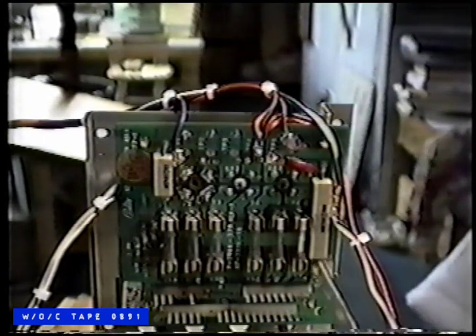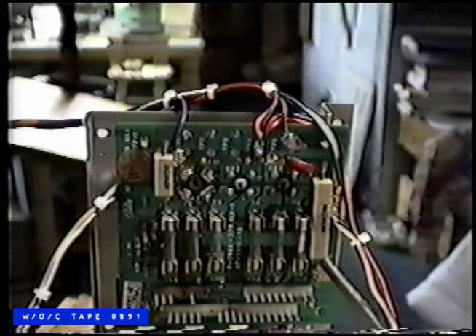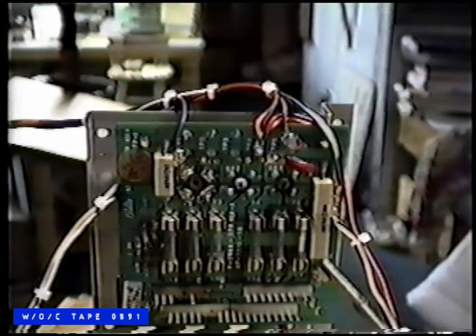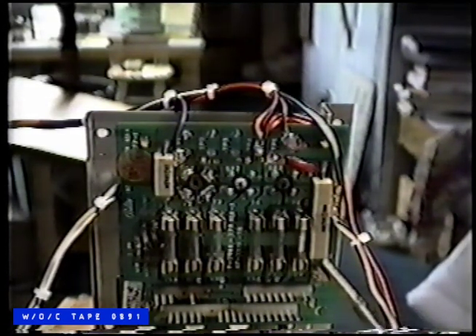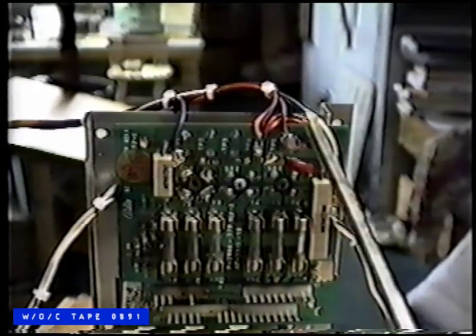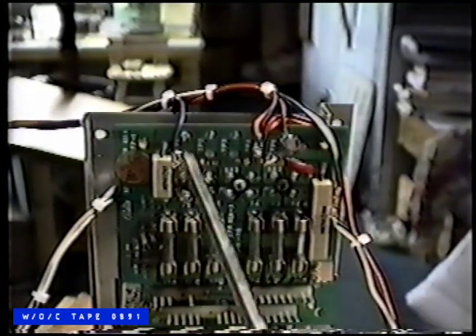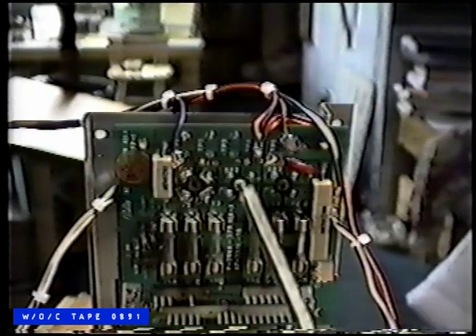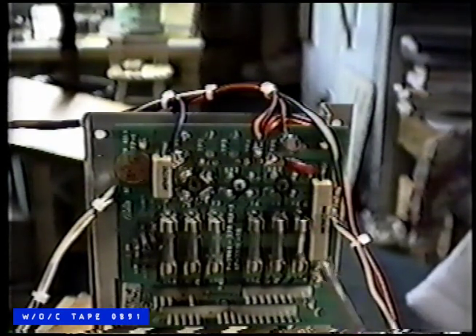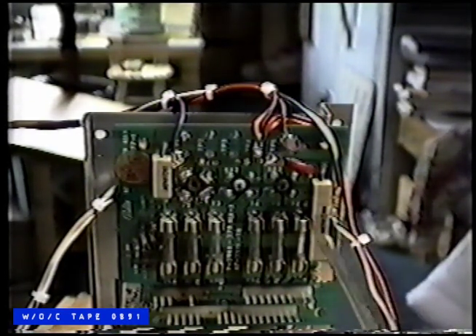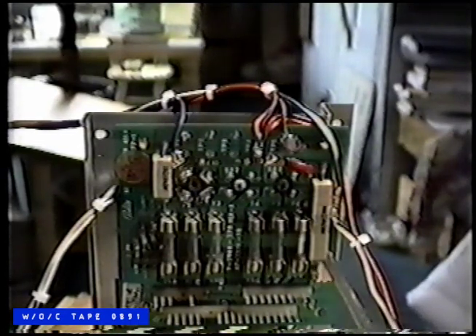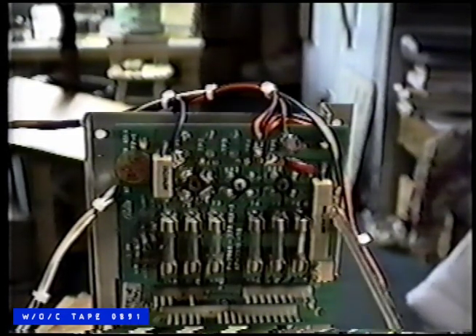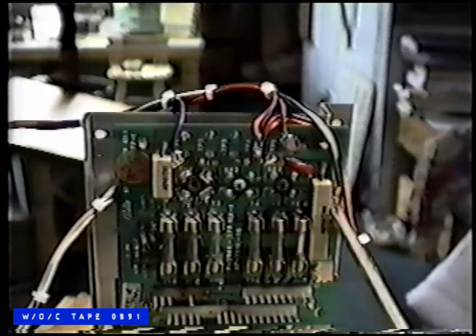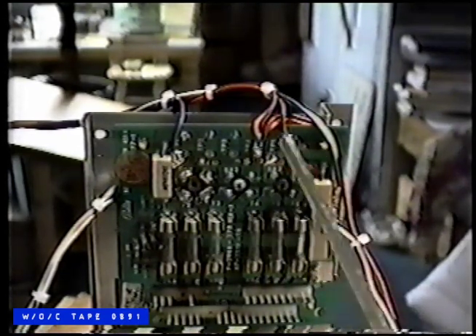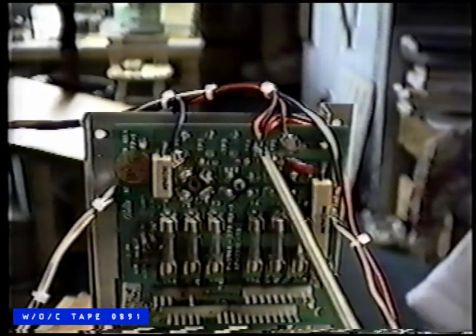So what you want is to use an insulated alligator clip right underneath there where it joins on, and you get yourself a really good contact, and then you can go do your DC checks up here to see if your voltages are alright. When you do an AC check, you can use that same ground pad that we showed you, and you can just simply change the meter over to AC to make sure your AC voltages are up.